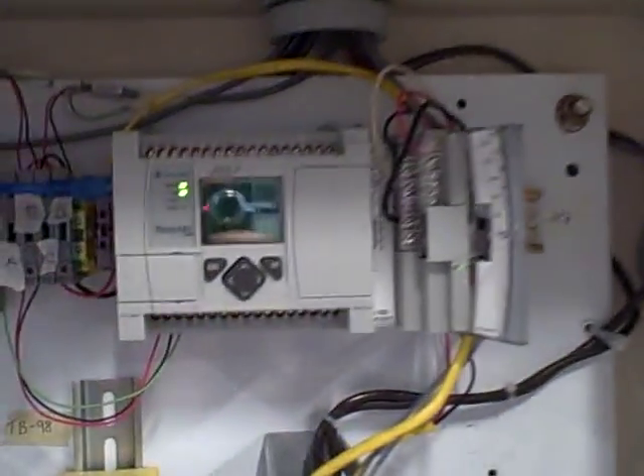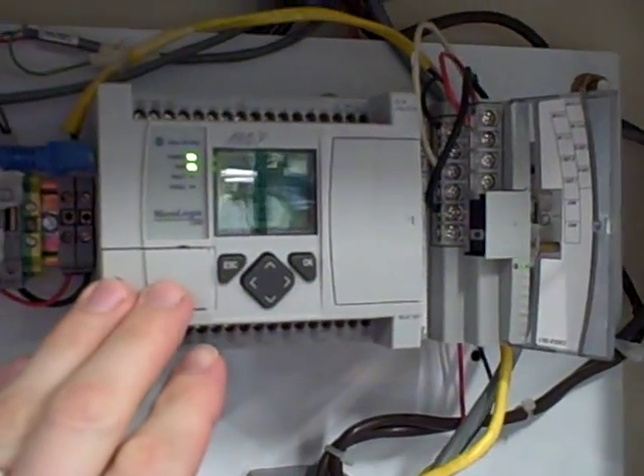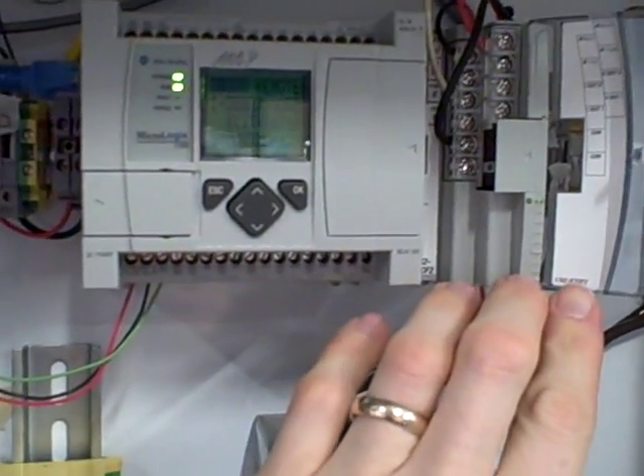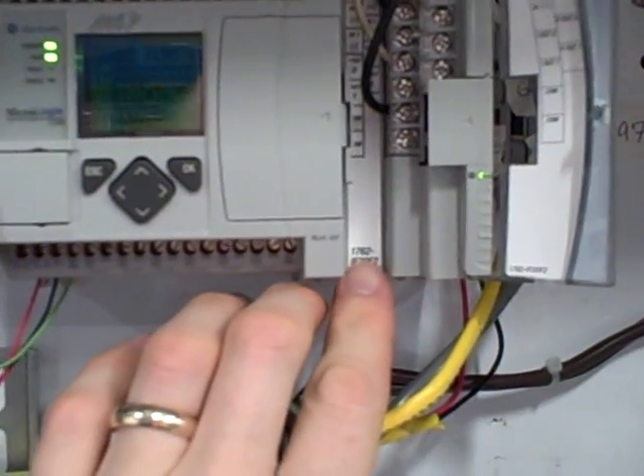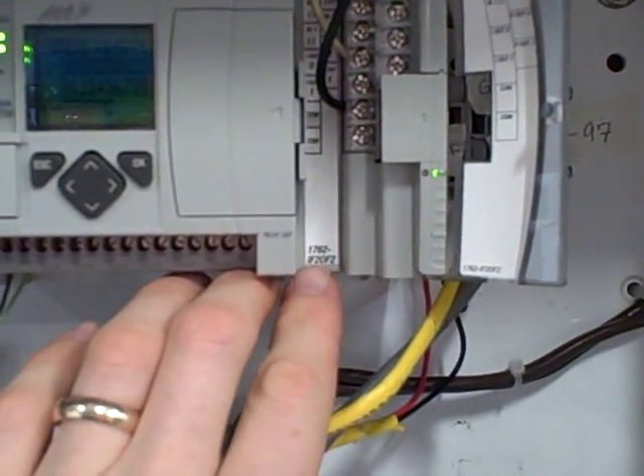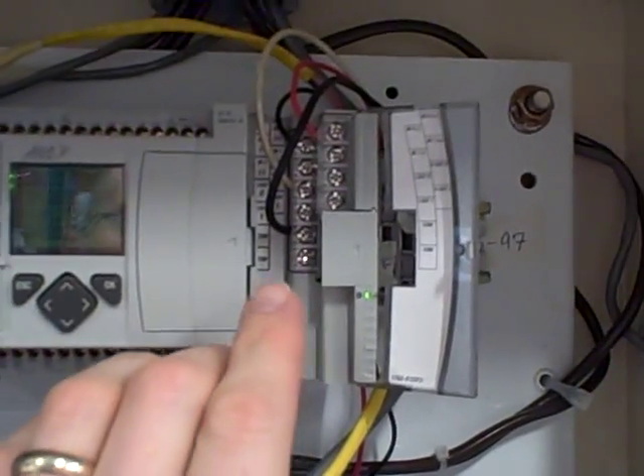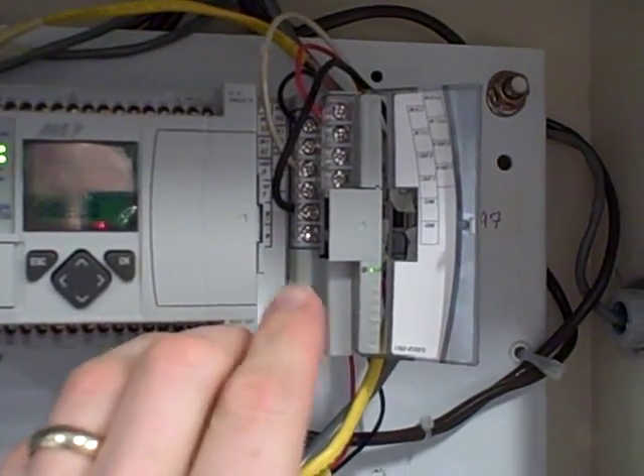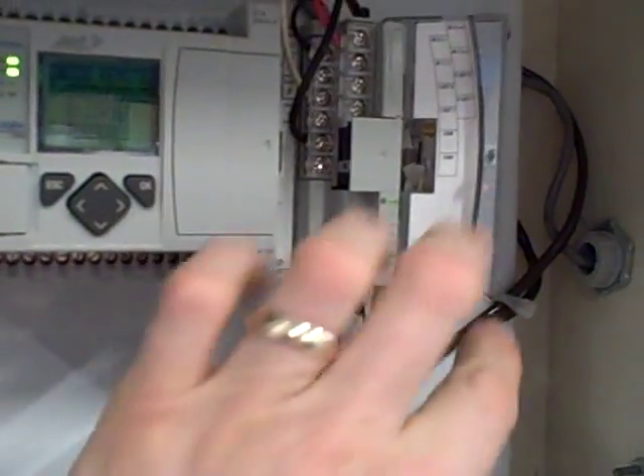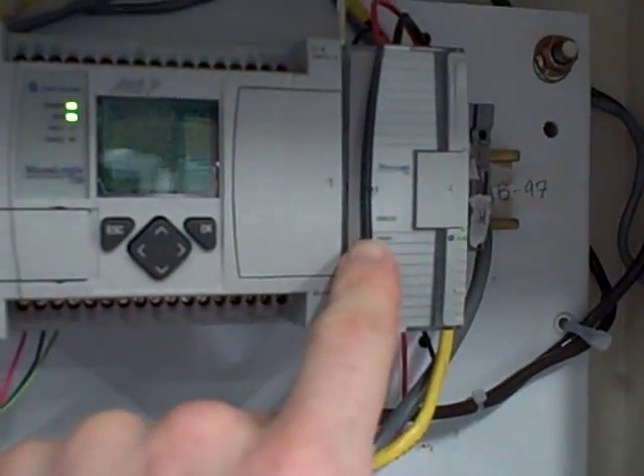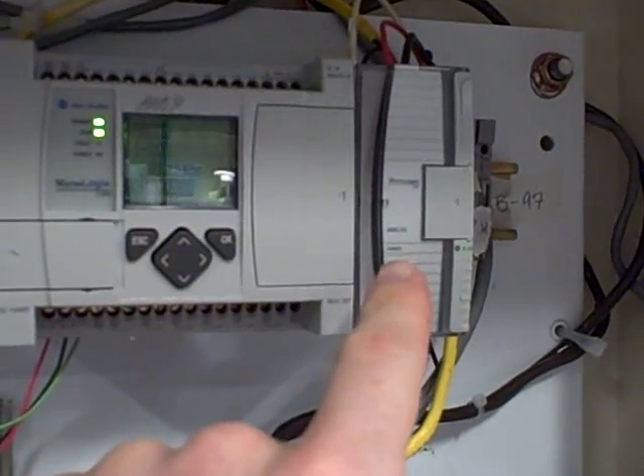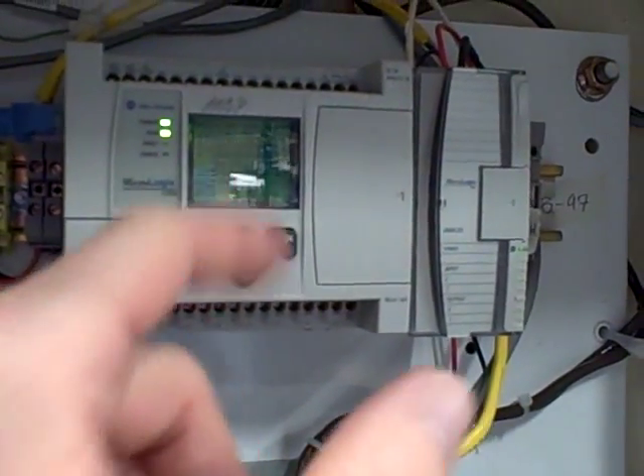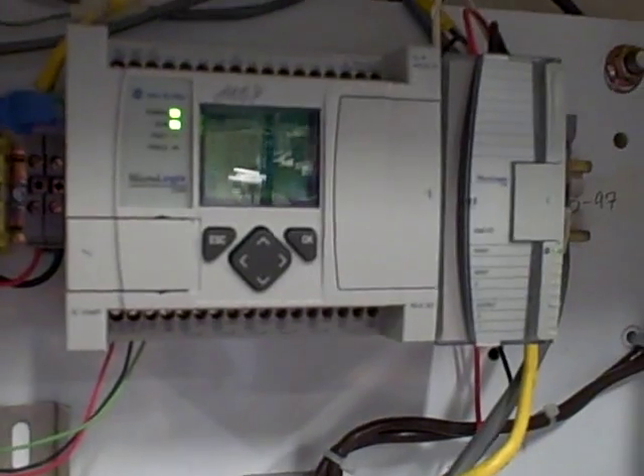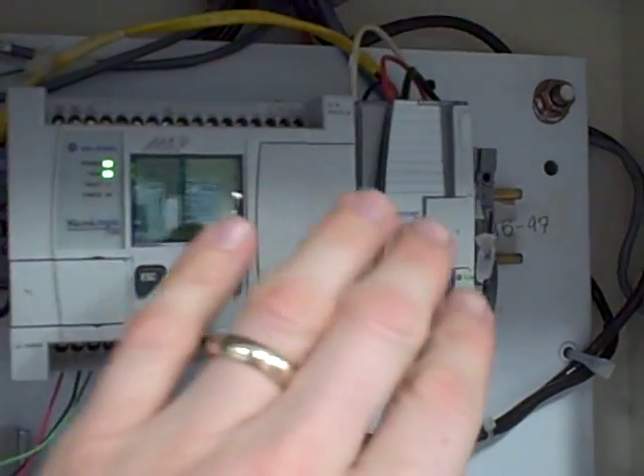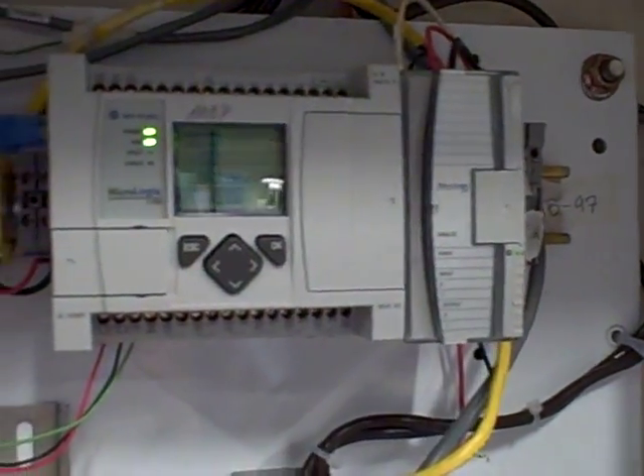So looking at the enclosure here, we see the Allen-Bradley unit. This is the 1100 unit. And attached to it, we have an analog input-output module. This happens to be a model 1762 IF2 OF2. Two channels of analog input and two channels of analog output. That communicates to the PLC, converting the 4 to 20 milliamp data for process variable into a signal that the PID instruction can understand, and then also from the output of the PID instruction back into 4 to 20 milliamps out to our valve positioner.